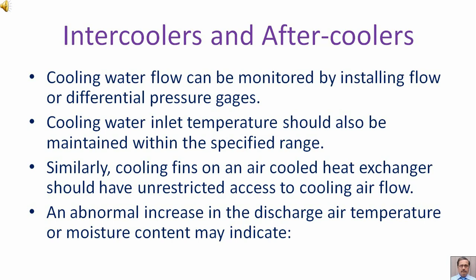Cooling water inlet temperature should also be maintained within the specified range. Similarly, cooling fins on an air cooled heat exchanger should have unrestricted access to cooling air flow. An abnormal increase in the discharge air temperature or moisture content may indicate issues as shown in the following slide.